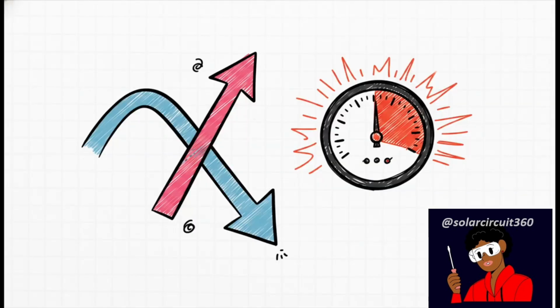What this means dynamically is that as voltage approaches that absolute maximum 58.4 volt limit, the physical behavior of the battery changes. According to the power equation, power equals voltage times current, as the cell gets closer to its maximum capacity, the current naturally tapers down, but the cell voltage starts rising much faster for every single amp you inject. The battery basically becomes highly, highly sensitive.